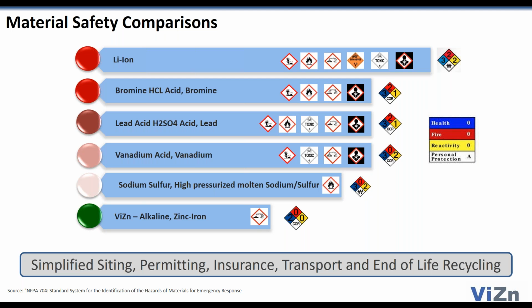As materials become more and more reactive, you become more and more regulated. Lithium ion is one of the more reactive materials. It's not allowed to be transported—no batteries are allowed to be transported with voltages over 60 volts in any configuration. Lithium ion batteries have to be transported as modules and assembled on site into packs, otherwise the voltages get too high. The same applies to a number of other batteries. The acidic batteries, particularly bromine and lead acid, have heavy metal toxic components, and they're regulated for emissions and access to buildings, for both fire code and safety code locally.